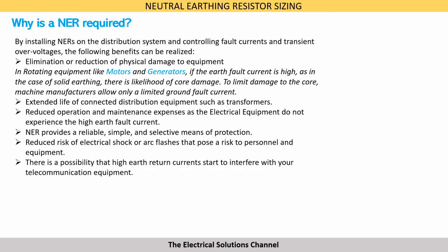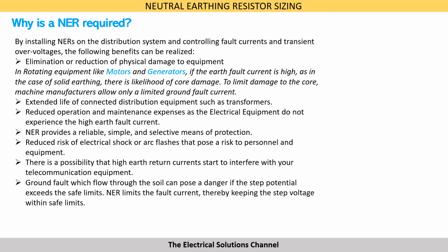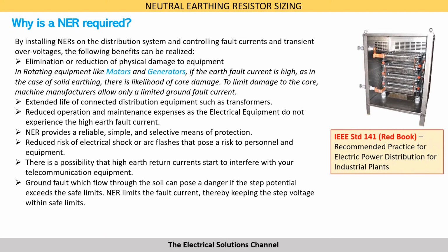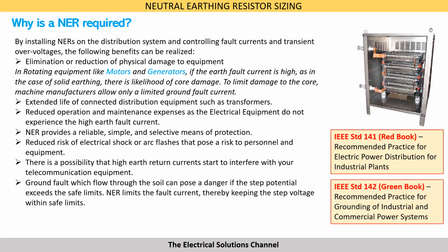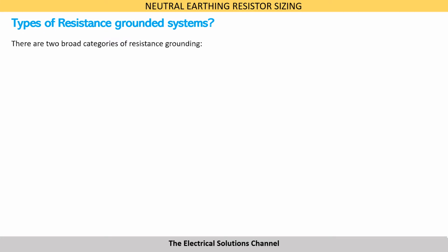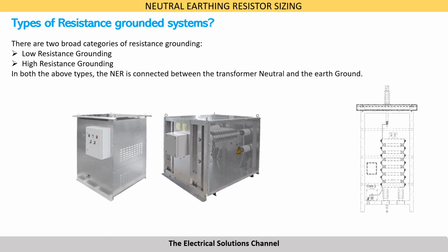If an NER is not there, then there is a possibility that high earth fault return current starts to interfere with your telecommunication equipment. Ground fault current which flows through the soil can pose a danger if the step potential exceeds the safe limit. NER limits this fault current, thereby keeping the step voltage within safe limits. There are two broad categories of resistance grounding: low resistance grounding and high resistance grounding. In both the types, the NER is connected between the transformer neutral and the earth ground.